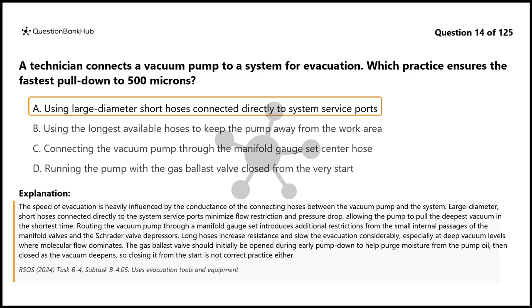Routing the vacuum pump through a manifold gauge set introduces additional restrictions from the small internal passages of the manifold valves and the Schrader valve depressors. Long hoses increase resistance and slow the evacuation considerably, especially at deep vacuum levels where molecular flow dominates. The gas ballast valve should initially be opened during early pump down to help purge moisture from the pump oil, then closed as the vacuum deepens, so closing it from the start is not correct practice either.